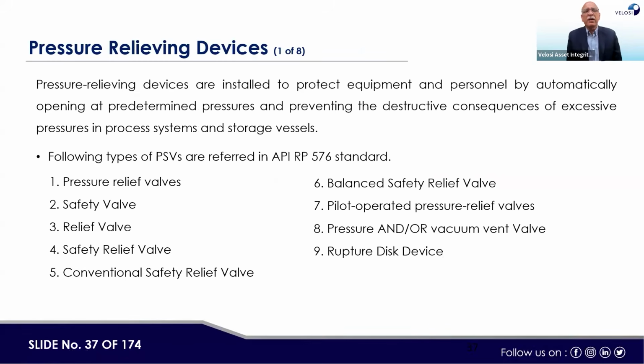Then, what are the pressure relieving devices? There are various kinds of PSVs or rupture discs which are used. Generally, there are four types. Number one, conventional PSVs. Then there are balanced bellows type PSVs or PRVs, then pilot operated, and then rupture discs. Here the terms include pressure relief valve, safety valve, process safety valve, relief valve, pressure safety valve, safety relief valve, conventional safety relief valve, balanced safety valve, normally called balanced bellows, then pilot operated pressure relief valves, then pressure and/or vacuum vent valves, and rupture disc devices.